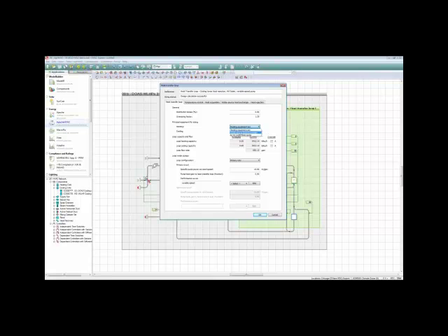If I select that, you'd see that both this one and this one will change, and I'll first talk about the other one. Over here on the cooling side, we can reject heat either with a cooling tower or fluid cooler, and/or with a water source heat exchanger, and we can nominate either of those to be the principal device for sizing. So if I go to the water source heat exchanger, it changes both of these.